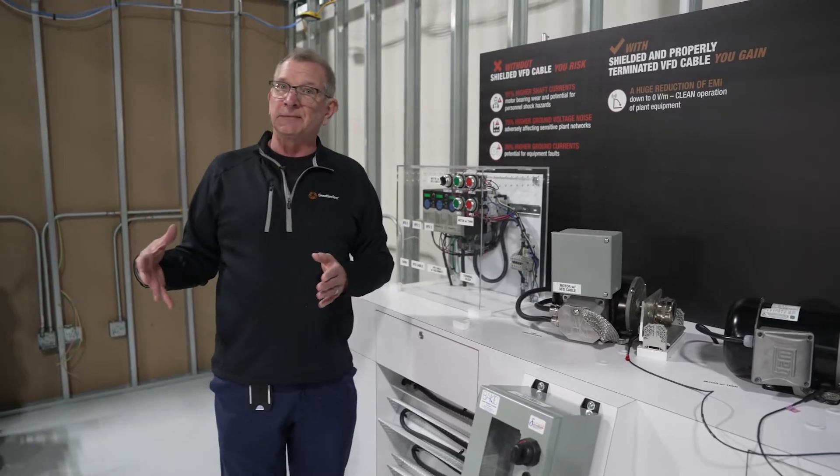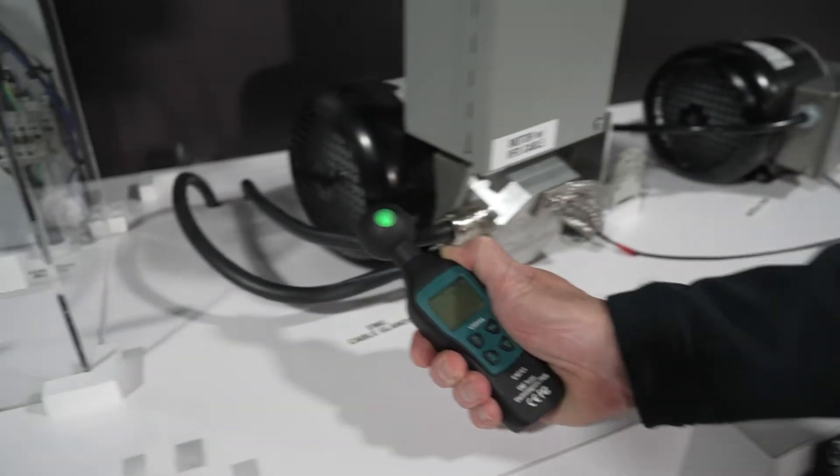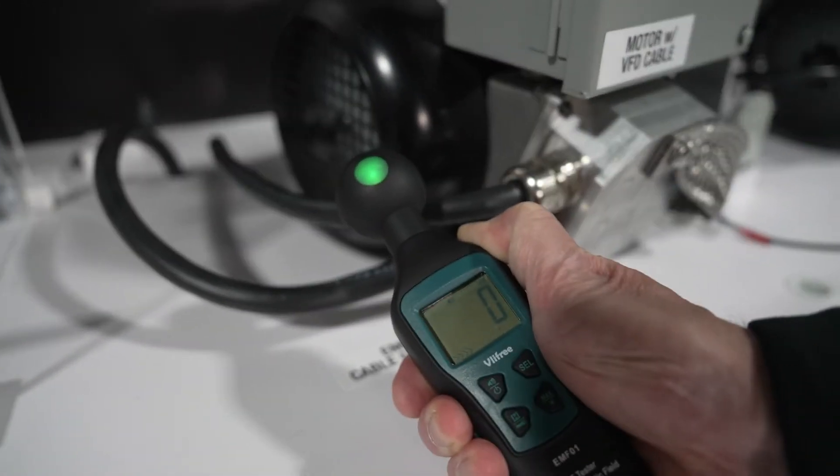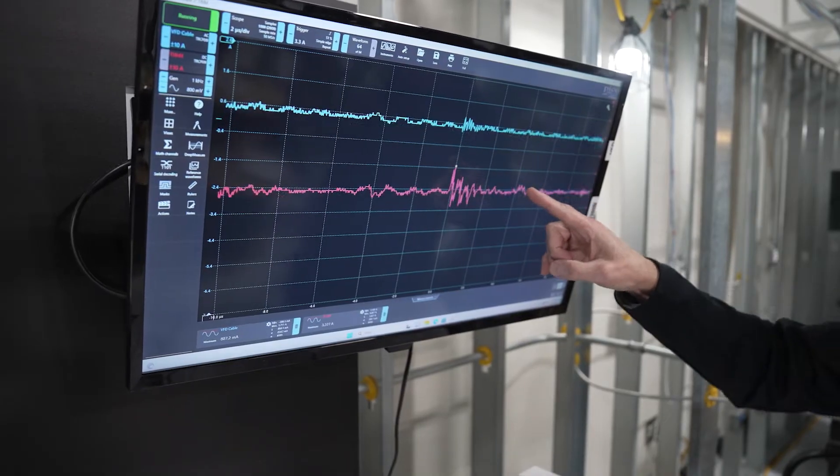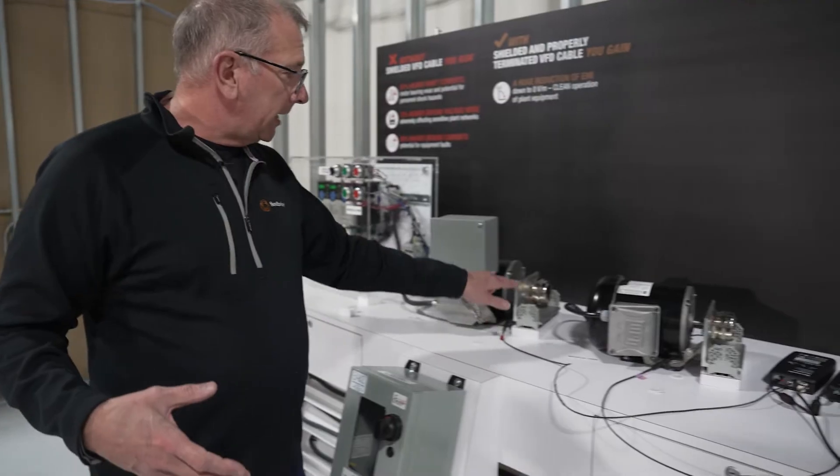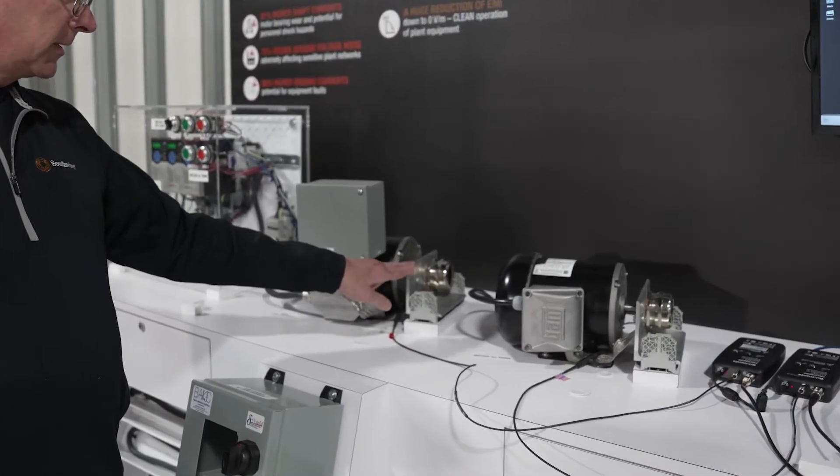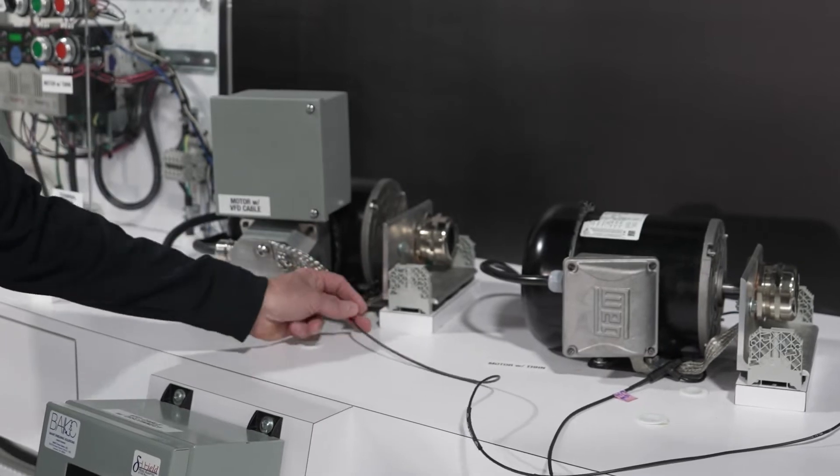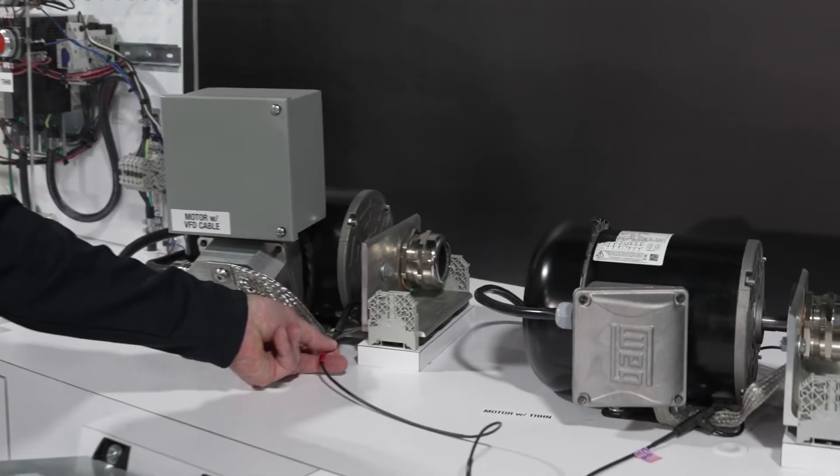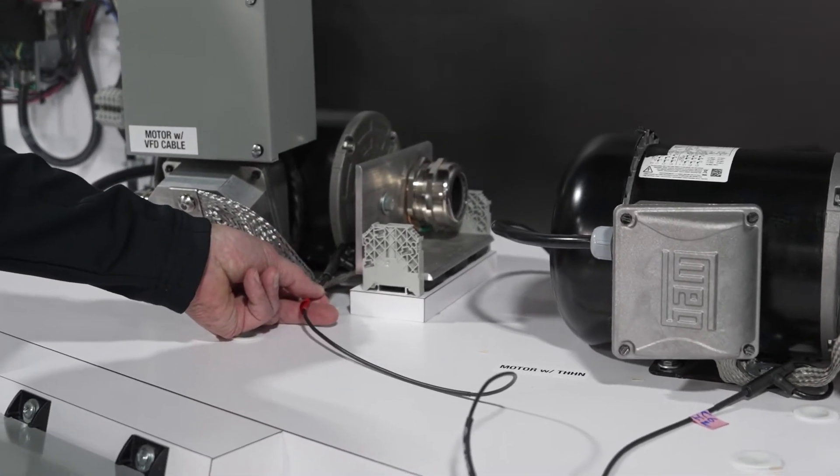We're going to take a look at a couple different parameters. We're going to look at EMI, Electromagnetic Interference, and we're going to also look at motor shaft currents. We're measuring the shaft current because we bonded these shafts to this plate here, and we're taking a current probe and measuring the current going to ground from the motor shaft.